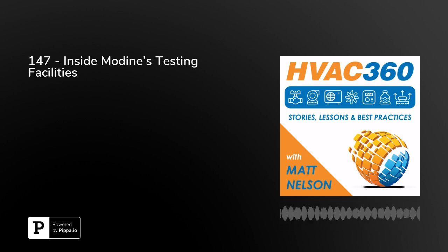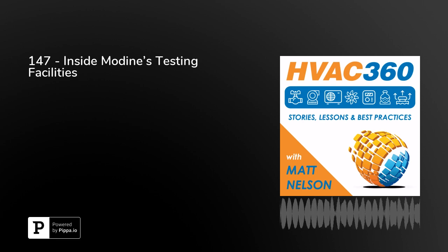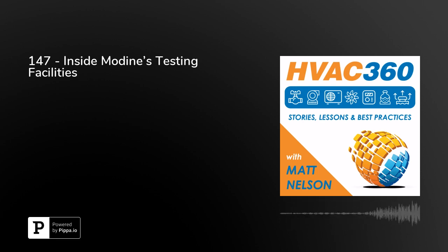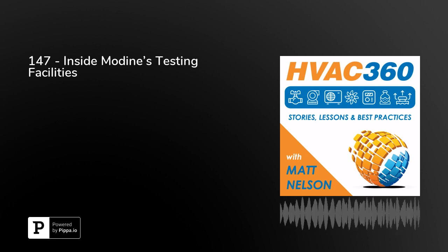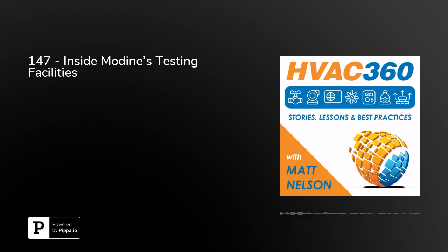Like our rooftop units, when you talk rooftop, a lot of people know EER, IEER, which is all governed by AHRI 340/360, which we do test to. That one basically sees the highest temperatures from a rating point standpoint at 95 degrees F, and then an 80 degree dry bulb and 67 degree wet bulb return air. So we do some of that testing, along with a 115 degree ambient hot startup type condition.